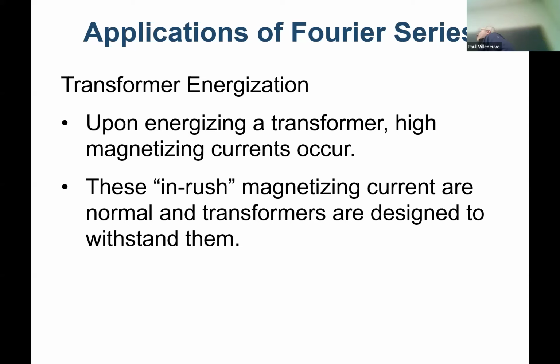They were done with the outage, and they wanted to close the transformer back in. They closed in, energized the transformer, and it instantaneously tripped. Actually, no, that was on neutral overcurrent. It tripped on neutral overcurrent. I was like, oh, this is a 660 MVA. This is inside of a mountain. So repairing it was not easy.